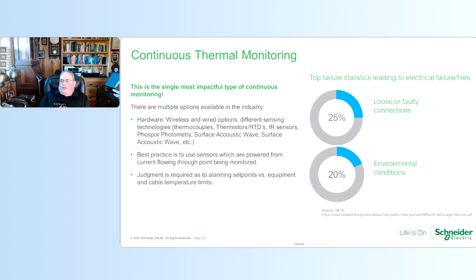So let's start with continuous thermal monitoring. For electrical distribution equipment, thermal monitoring is the single most fundamental and impactful continuous monitoring system that can be added. And the reason is because heat is the enemy of insulation materials. And by monitoring the temperature of cable terminations, busing, and the equipment internal and external temperatures, the presence of detrimental sources of heat, such as suboptimal electrical connections, can be detected. This is really where the rubber hits the road. It's been shown that 25% of events leading to electrical failure or fires are due to loose or faulty connections, and 20% are due to environmental conditions such as ambient temperature and humidity. All of these will show up if appropriate continuous thermal monitoring is applied.